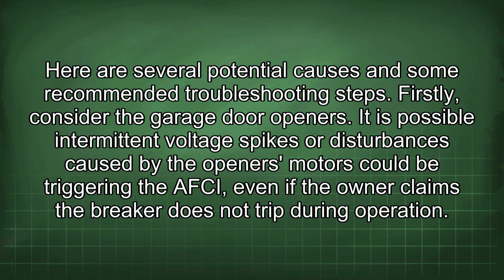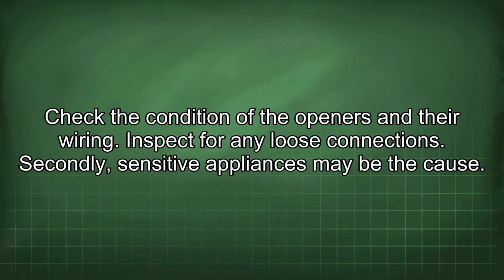Firstly, consider the garage door openers. It is possible intermittent voltage spikes or disturbances caused by the opener's motors could be triggering the AFCI, even if the owner claims the breaker does not trip during operation. Check the condition of the openers and their wiring. Inspect for any loose connections.